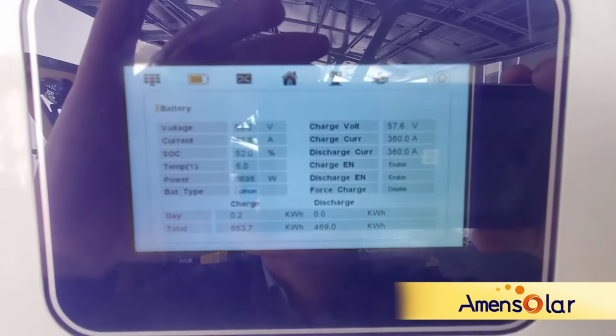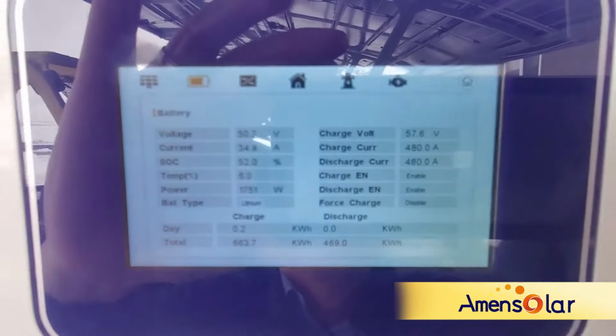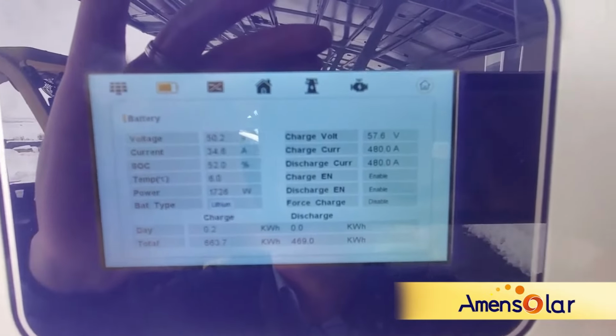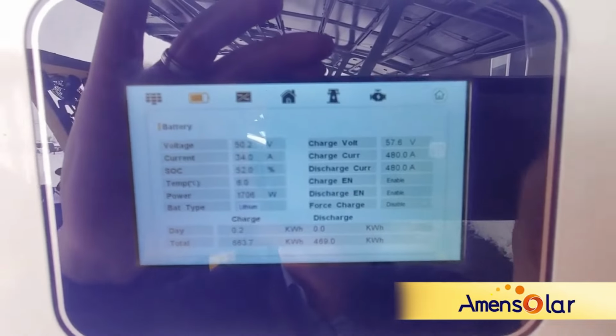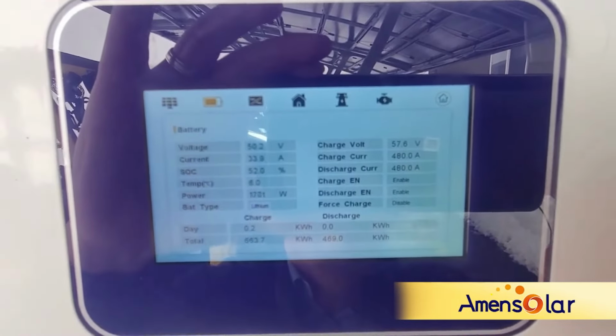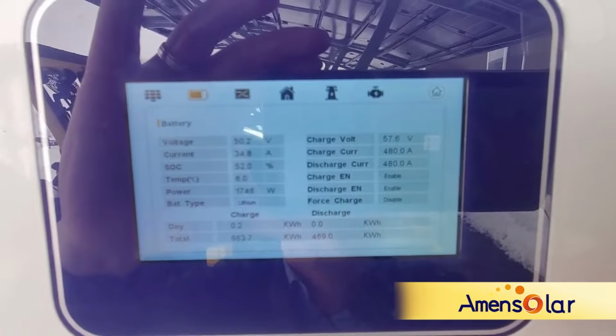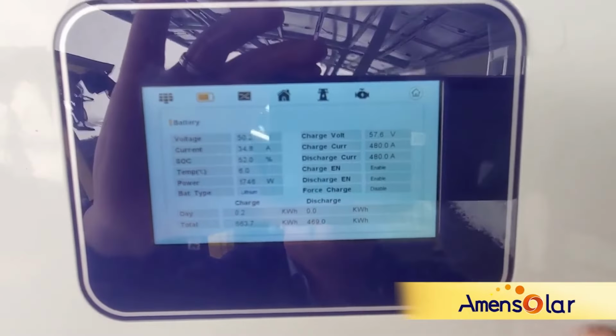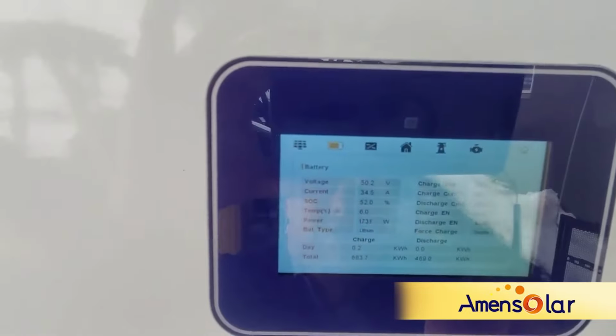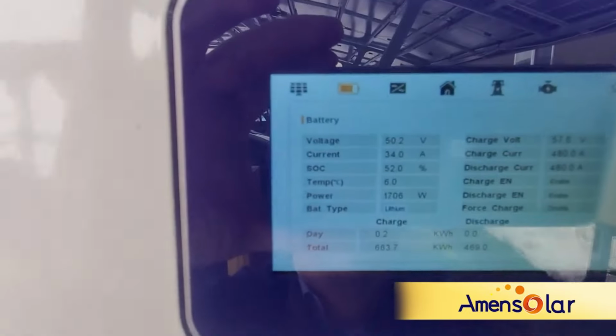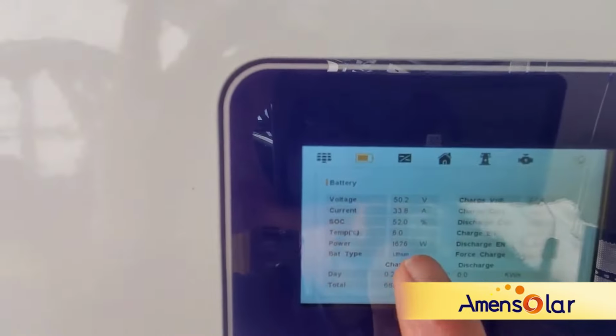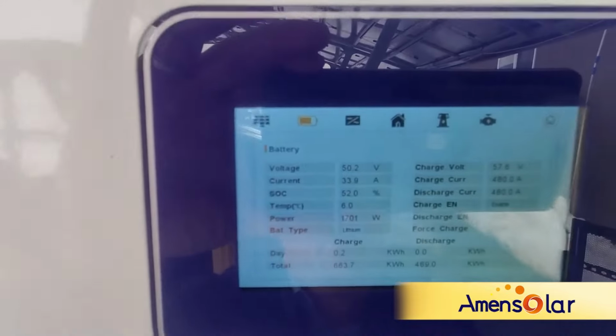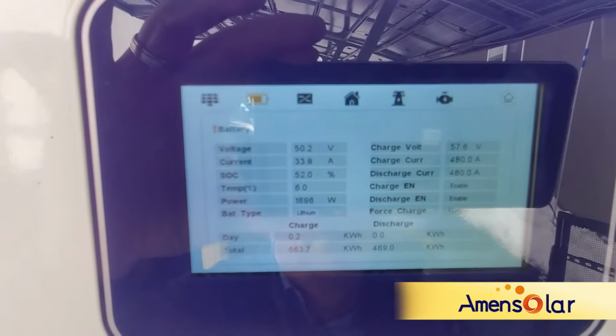This is why BMS communication is pretty important, because it reads from the BMS how many amps it can charge and discharge with. Right now it's 480 amps, the maximum capacity it knows it can charge and discharge at. Even though this inverter can only do 190 amps maximum, at least it knows the capacity and the state of charge of the batteries, and sees how many amps are going in charging the battery right now.